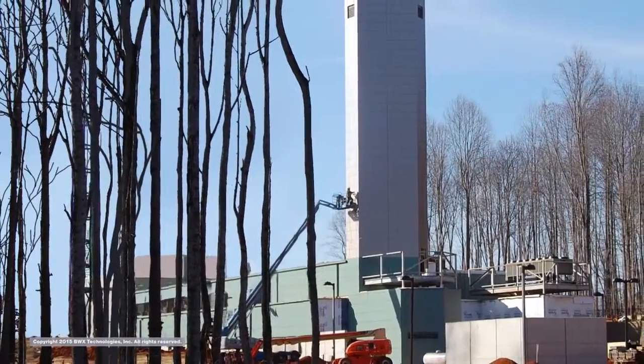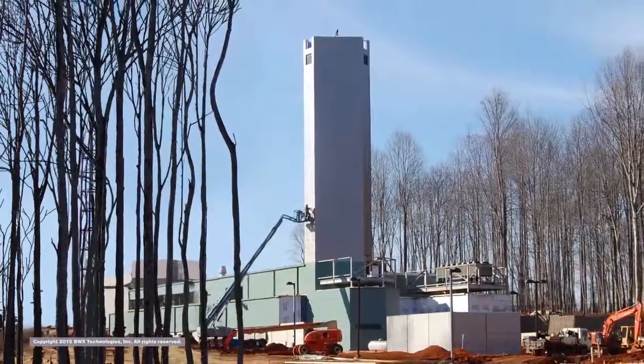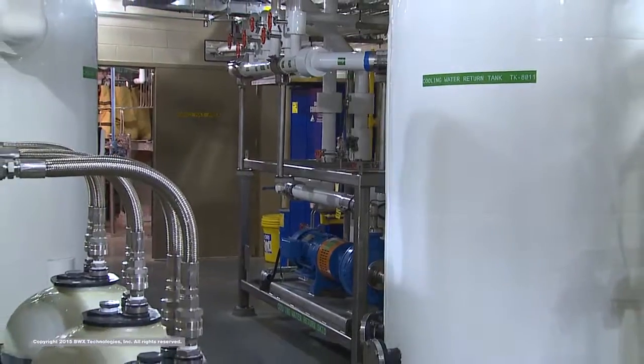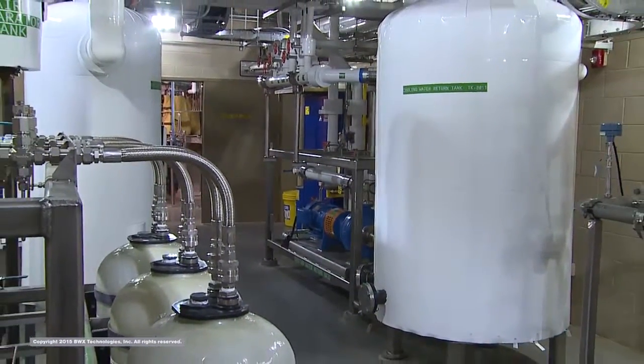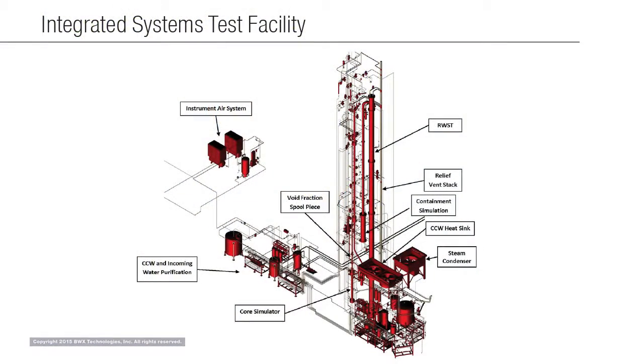The facility was commissioned and fully pressurized in August 2012. The IST consists of a primary flow loop with all the components of a traditional pressurized water reactor primary coolant system represented. The vessels are fabricated per ASME boiler and pressure vessel code, with a maximum design pressure of 2500 pounds per square inch and temperature of 650 degrees Fahrenheit.